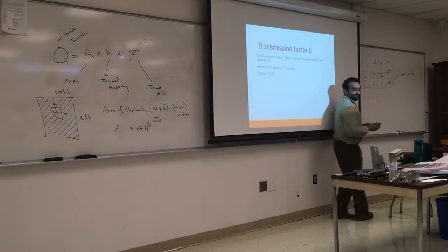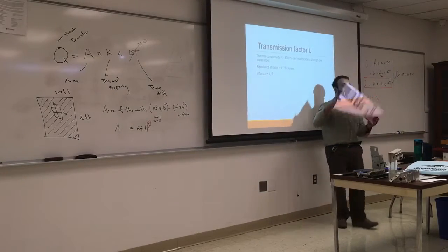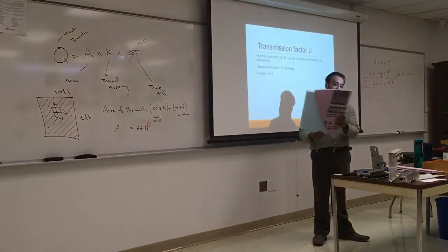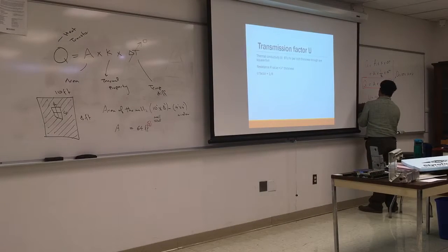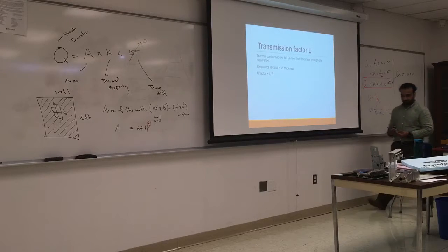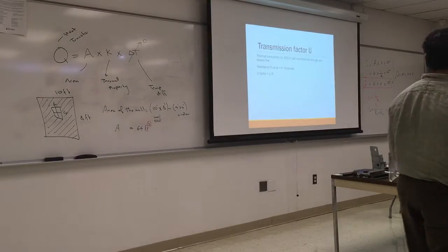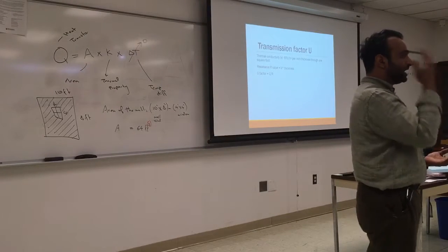One piece. If I took this board, which has an R value of 4, and I doubled it, it is how much? 8. But I want to put another board here, which is around 6. So I'm going to put those two, so we have 4 and 6, that's 10. So I want to get the U factor out of that. It's like making a sandwich, keep adding layers, it's going to add up. Again, write it down, you don't have to memorize it, put it on a cheat sheet. I just wanted you to understand how it should make sense to you.